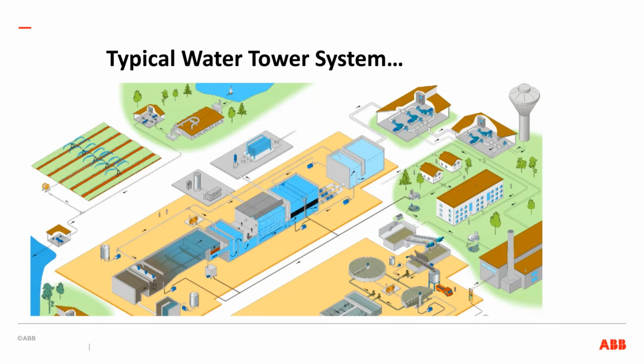There's not really a code requirement calling out for water towers, but it does give us the ability to store water high, so we have water pressure built into the system. But it's a drop in the bucket when we look at the millions of gallons of water in the distribution system below ground versus what's really above it. But with a water tower, we can replace that with ground storage, or we can continue to use it, and we can use the variable frequency drive. There's only one pipe in a water tower, and it's up or down.